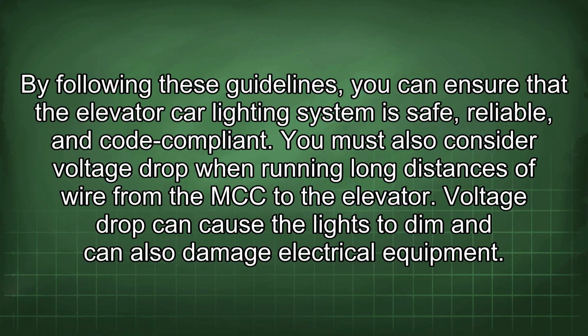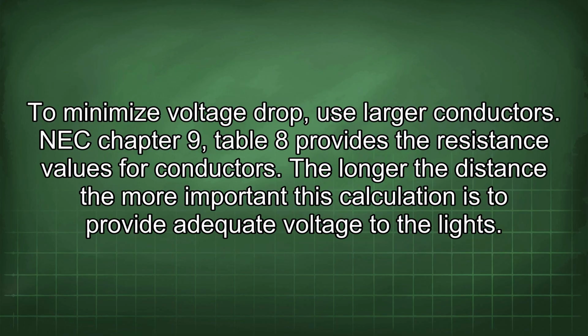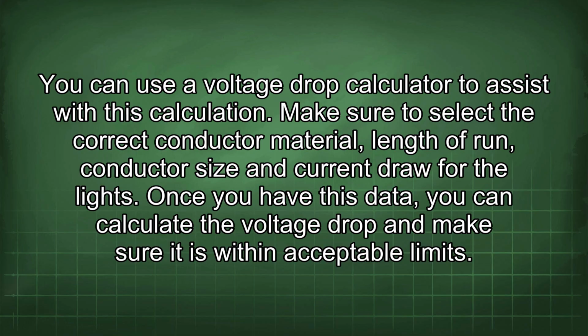You must also consider voltage drop when running long distances of wire from the MCC to the elevator. Voltage drop can cause the lights to dim and can also damage electrical equipment. To minimize voltage drop, use larger conductors. NEC Chapter 9, Table 8 provides the resistance values for conductors. The longer the distance, the more important this calculation is to provide adequate voltage to the lights. You can use a voltage drop calculator to assist with this calculation.